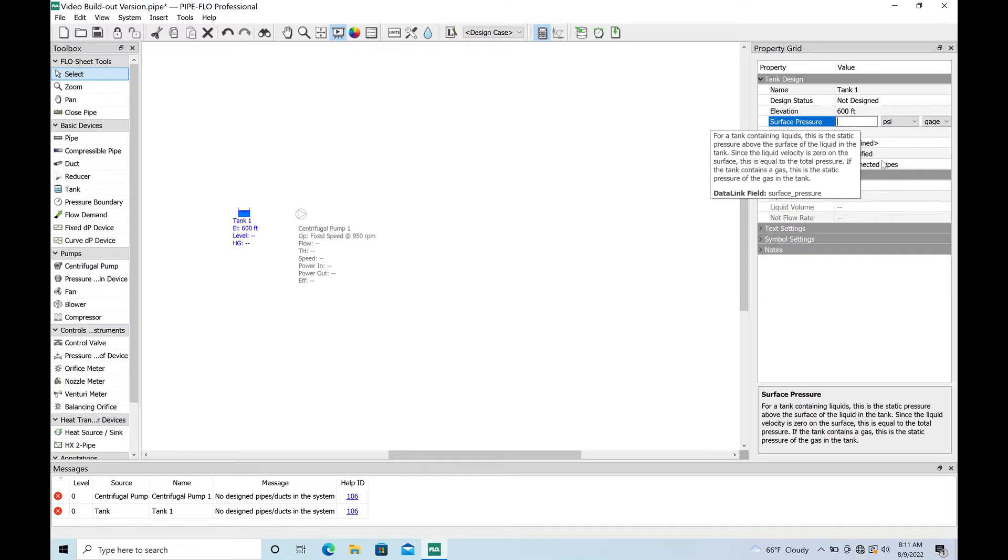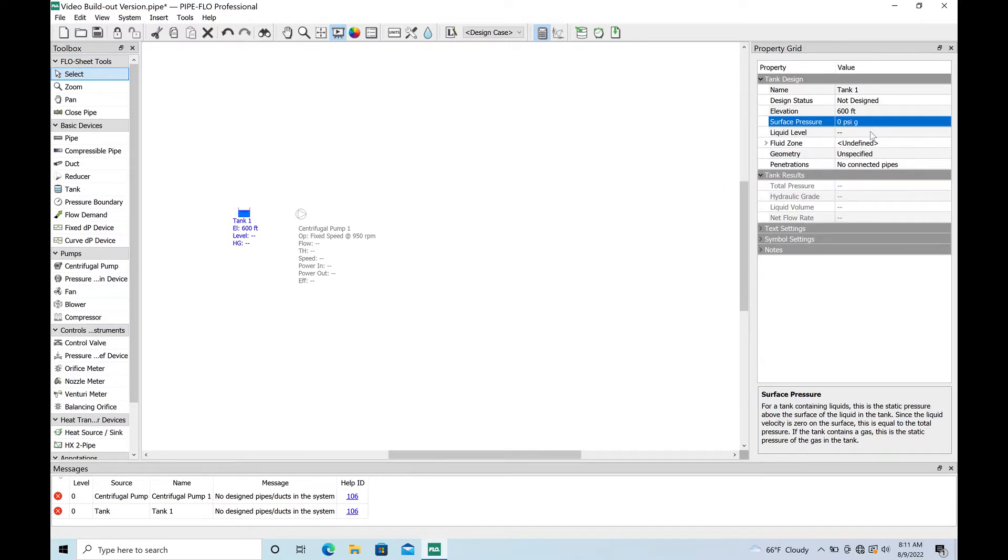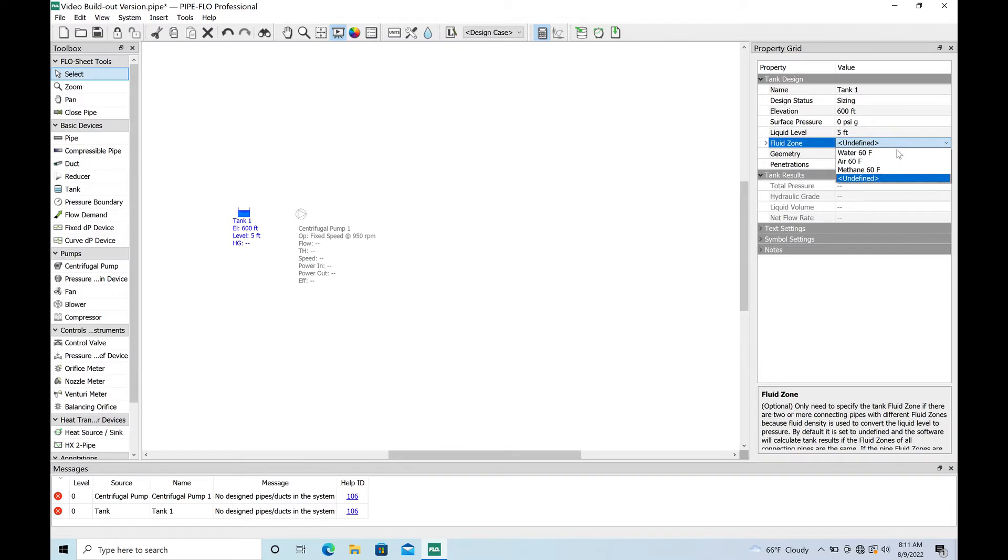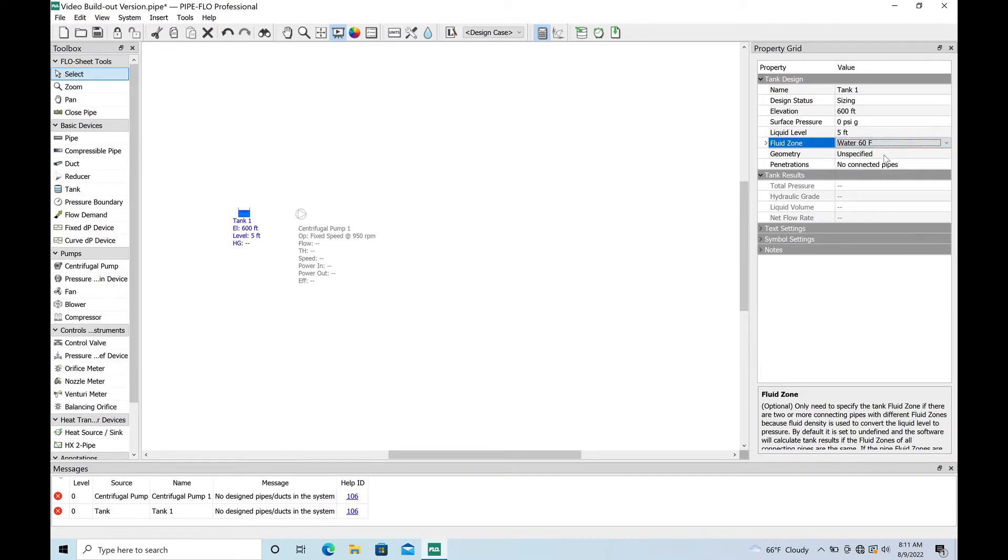You've got your tank, you need to put in an elevation for the bottom. Let's pretend like I'm pulling these from record plans because we're building a system that exists and we're going to check it. If you're building something new it would be the same. I'm going to say five feet for the tank for the submergence there, that way I've got some water over my pump. I'm not going to pull a vacuum or violate any NPSH issues.